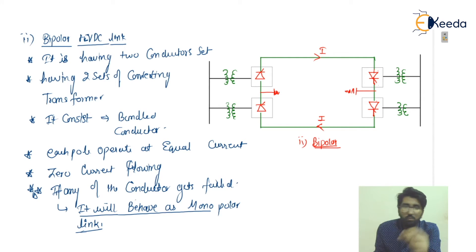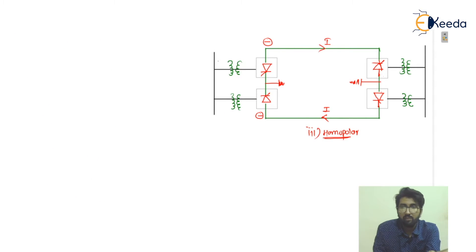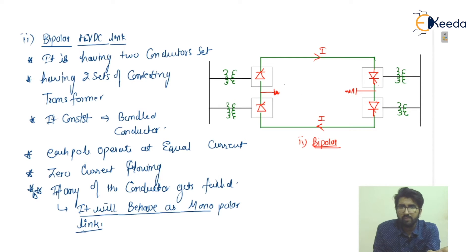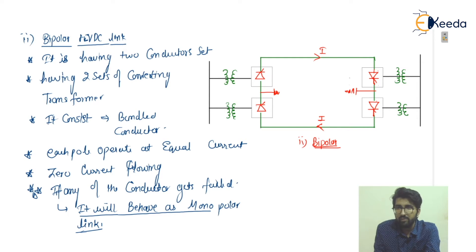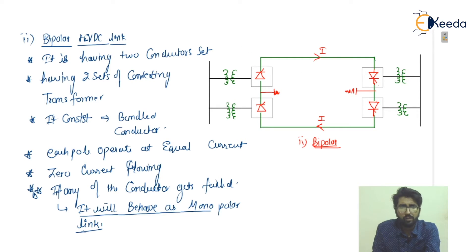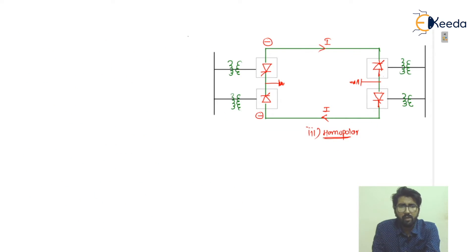One important point to add: the bipolar link is grounded at the midpoint. If the total voltage is V from one end to the other, then each conductor carries V/2. So the voltage value is halved — each pole has a voltage of V/2.